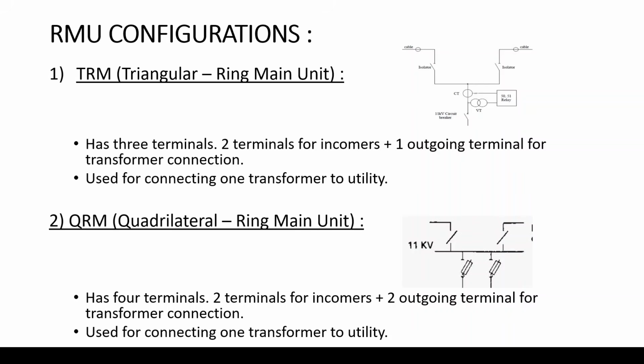Actually, it's not my decision. If my scope is not the HV, the decision is usually by the utility company to provide a suitable RMU for a certain project. So in this case, every RMU, regardless of the configuration, has 2 terminals in the incomer side, as you can see, because you want to connect your project to the ring. I have an incoming cable coming, let's say 11 kV, it's coming here. Then I have the outgoing cable continuing to the next load or to the next project or to the next RMU. So these two are standard for all RMUs. I have 2 terminals from the incoming side, and then I have the outgoing side feeding the distribution transformer. So here I have 3 terminals. It's a TRM, triangular RMU.